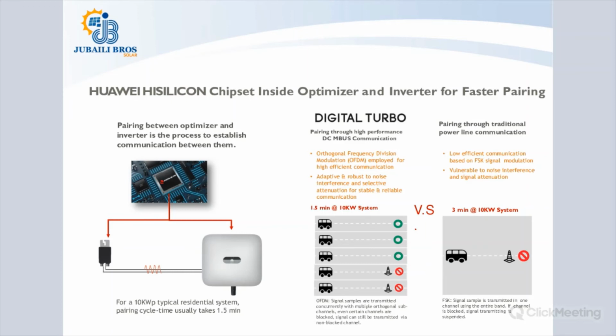You can see here there's a Huawei HiSilicon chipset, and this chipset is embedded in both the inverter and the Huawei PV optimizer. What it does is allow for DC MBUS communication systems to the PV optimizer. And these are M-bus systems, not like the traditional system that you know. So what does this chipset allow? It allows for multiple routes of communication to the inverter.